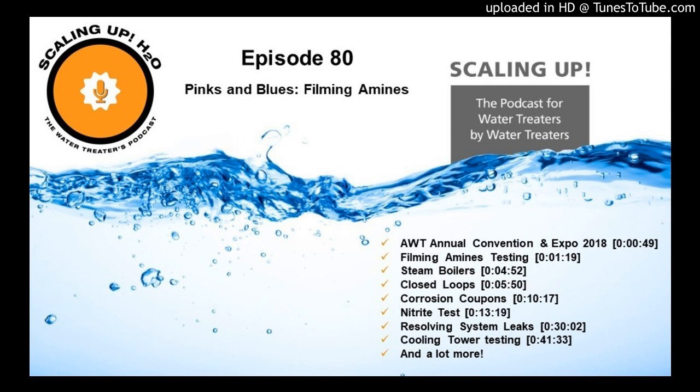So here's probably what you're saying. Well, Trace, I need to know how much of a residual that is because my company has those parameters and I need to either add or not add based on what those parameters are. Well, folks, I was not able to duplicate any results where I or anybody on my team feels comfortable that the results you're going to get after you put that prepared sample in your spectrophotometer are worth anything. And here's why I say that. We wouldn't just test one sample. I would have 10 samples in front of me, spaced apart so not a lot of time went by, and I could not get a repeatable result. And if I continued to test the same vial, I got different results.